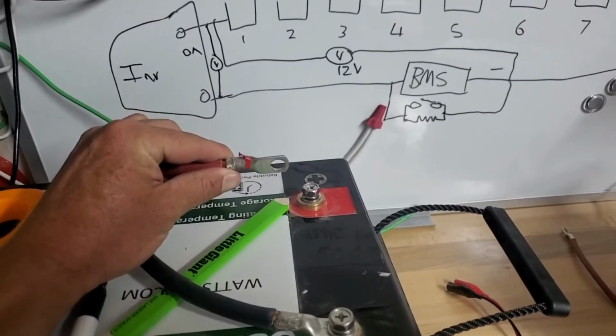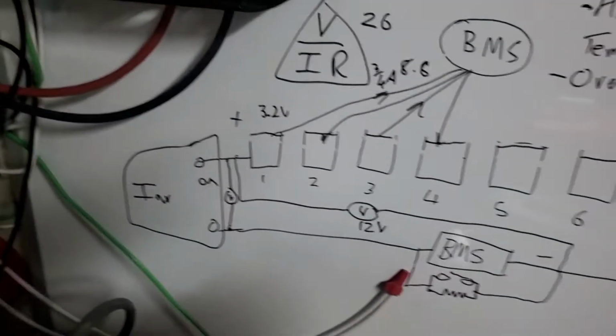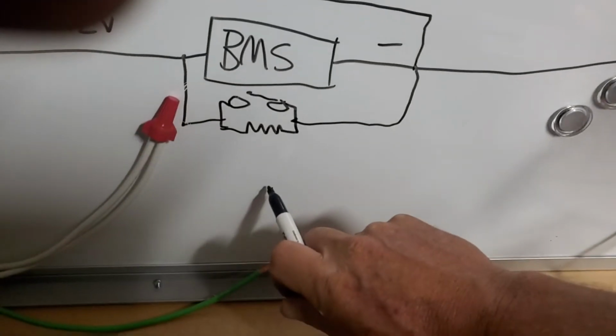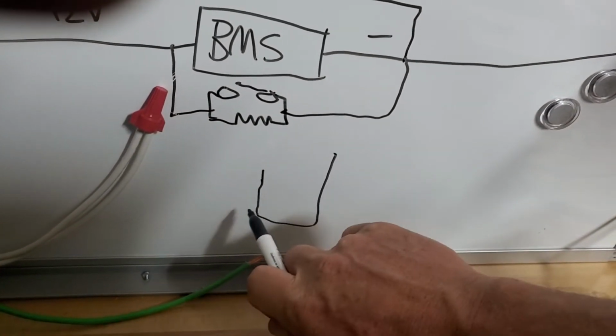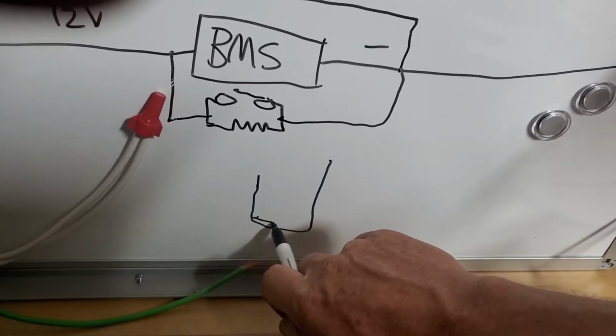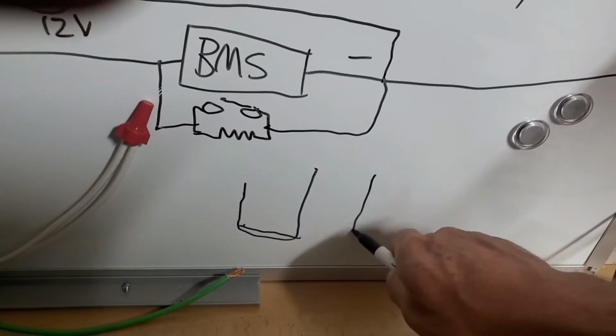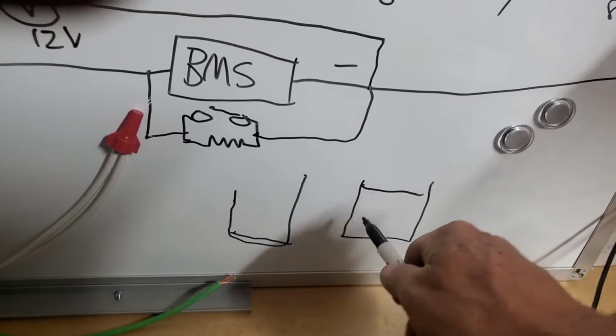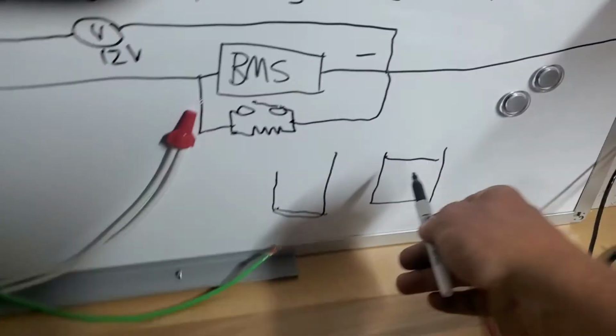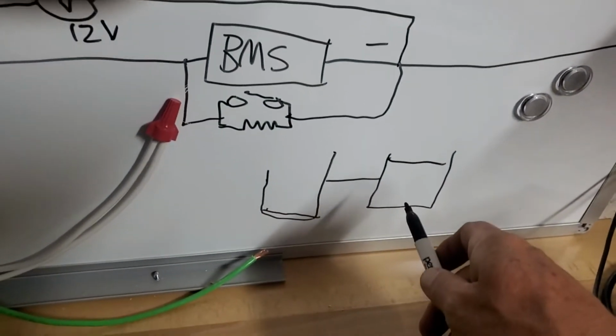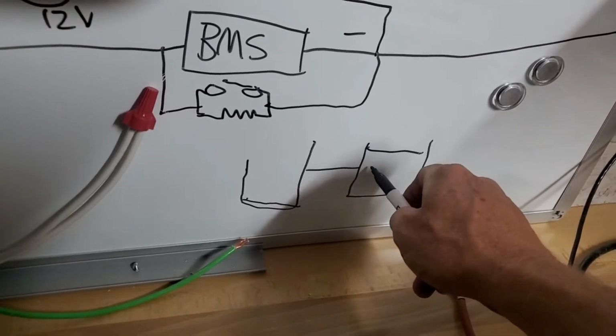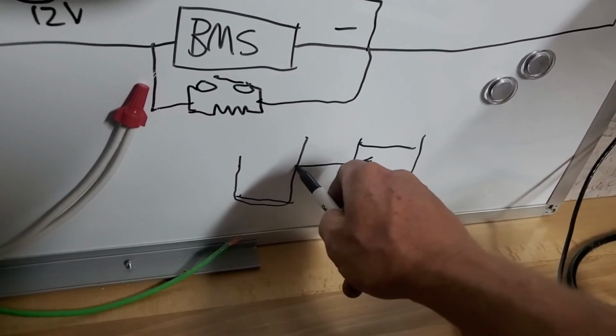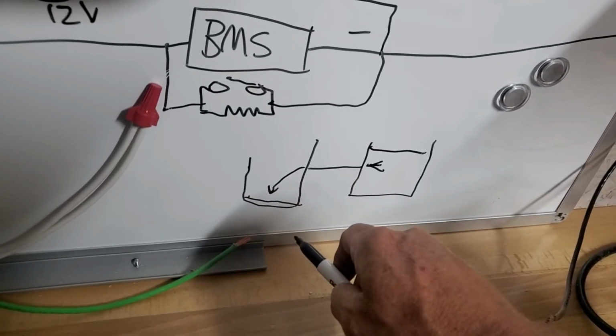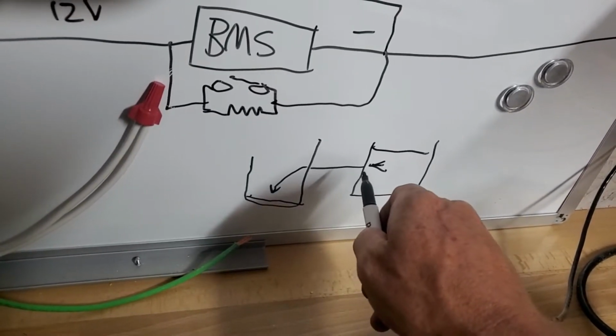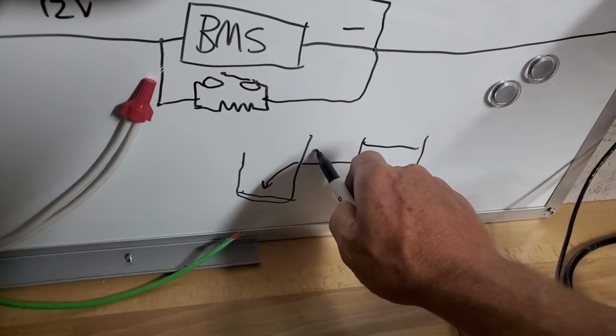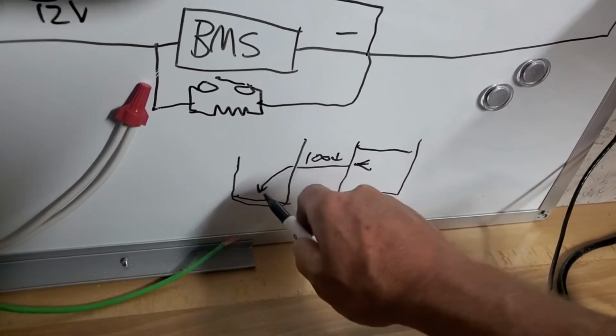In this inverter you've got some capacitors inside—let's just call it a tank that is empty. In the battery you've got a tank that is full. With these big fat wires we're connecting this tank to that tank, and this battery is going to try as hard as it can to fill up the tank over here. That's that big spark you see—all those amps, hundreds of amps, 100 plus amps flowing through there to try and fill that up.